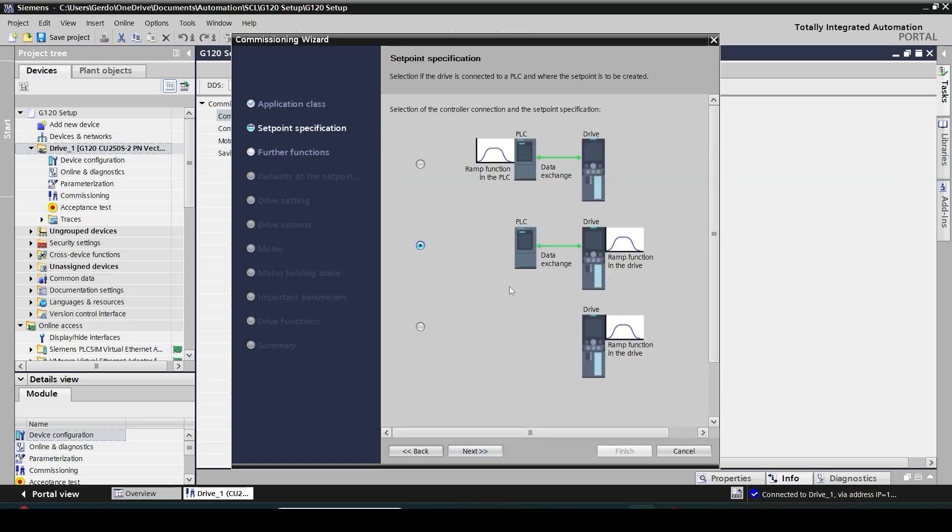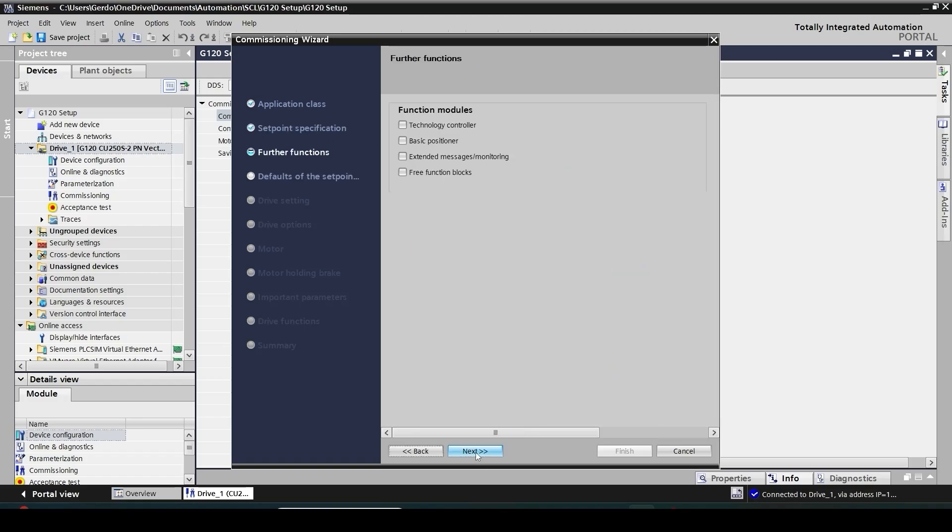Next, where the setpoint is going to be created. Basically it means the calculation for ramp function generation will happen in the PLC or in the drive, so in this case I'm going to do everything in the drive. That's the default. Next, do I have any specific extra function? Because some of the Siemens drives come with additional functionality built in, like a positioner inside or other things. In my case I don't have any additional functionality so I just make sure that all boxes are unchecked.